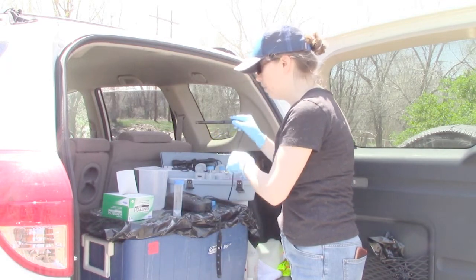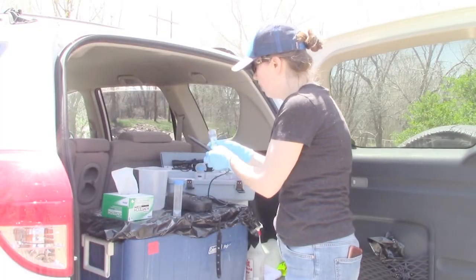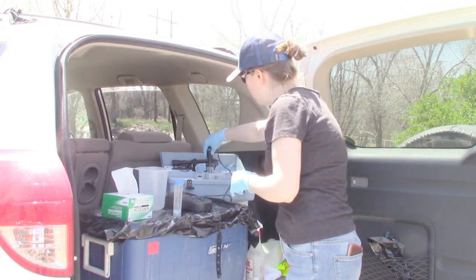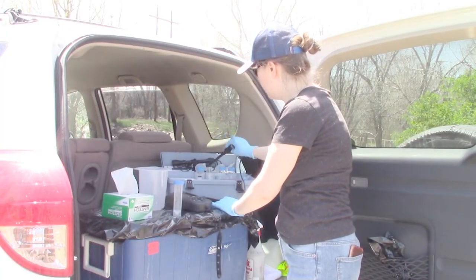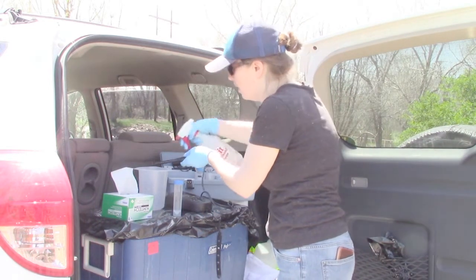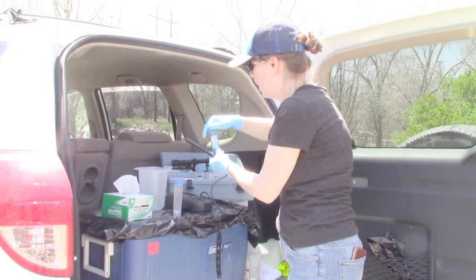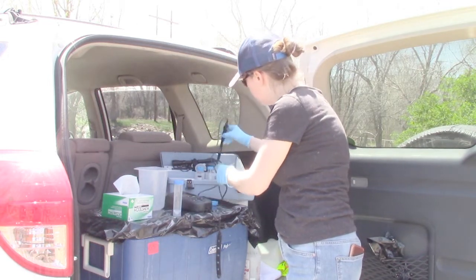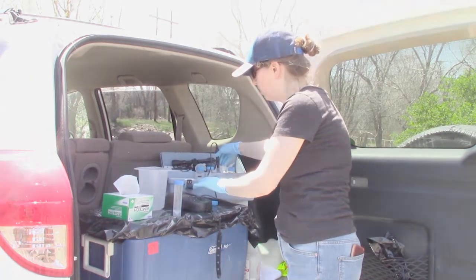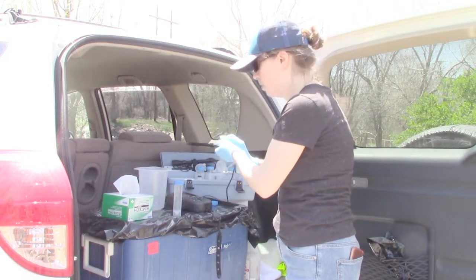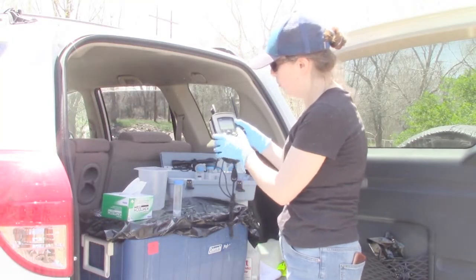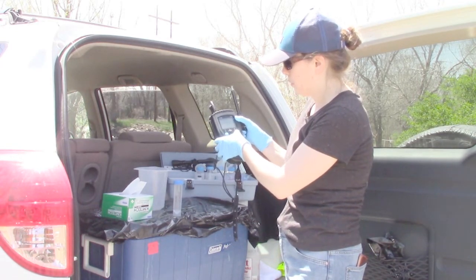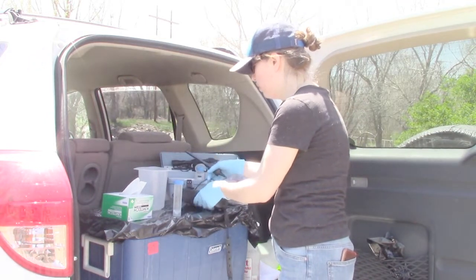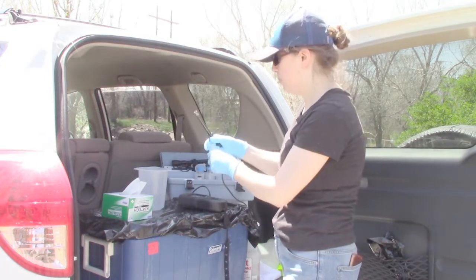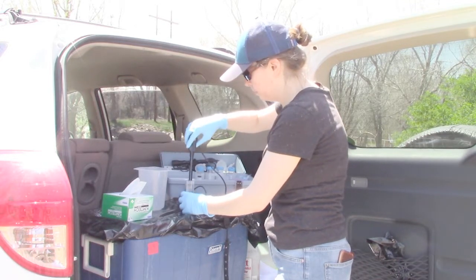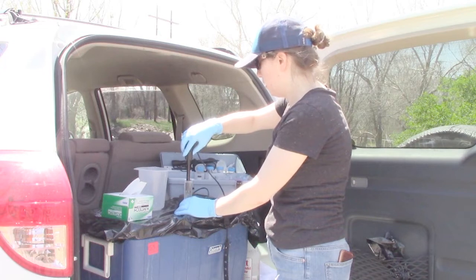So we're already there. You rinse the probe again and put it into the pH 7 calibrant solution. Press read again. You hear the beep, it's stable. It's at exactly pH 7 actually. That's great. The last one is pH 10. It's stable at 10.02. So that went pretty fast. Now you can push the done button and also push store. It's going to store that calibration, and you get to measure the pH of the sample you're interested in. And press read. So it's stabilized at 8.23.